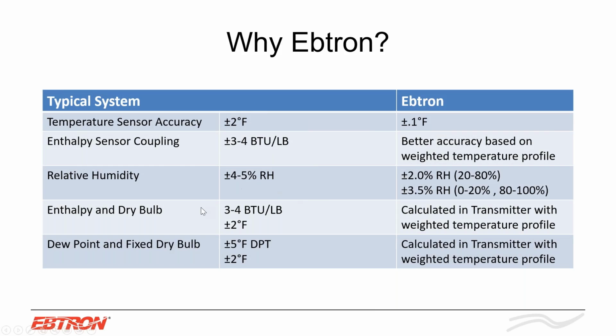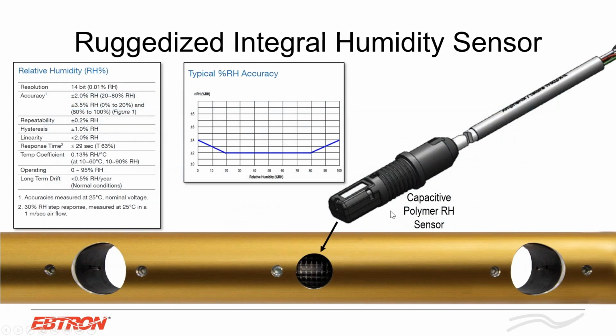And this is just typical system accuracy of sensors that you might be buying in the field versus the EBTRON unit. And again, I said EBTRON measures temperature to calculate flow. So we have to have a really accurate temperature sensor. So our first output is always flow. Our second output is temperature, which is a 0.1 degree F temperature sensor. And then our third output, we have the option for relative humidity, dew point, or enthalpy. So it's an extremely accurate device. And again, now you have 3 points going back to one transmitter.